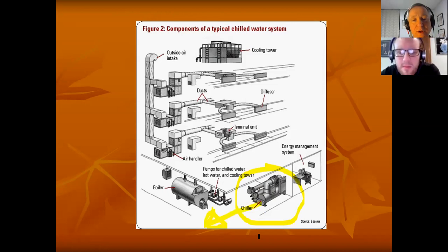So that's how you get rid of heat, and then you spray water in the cooling tower, and there's different types, but typically they have a fill, like a plastic material. You spray the water on there, and the small droplets evaporate more readily. There's more surface area exposed, and the water actually cools down about 10 degrees Fahrenheit during the operation in the cooling tower. So it's a really good way to cool things down. That's how you get rid of the heat produced by refrigeration.